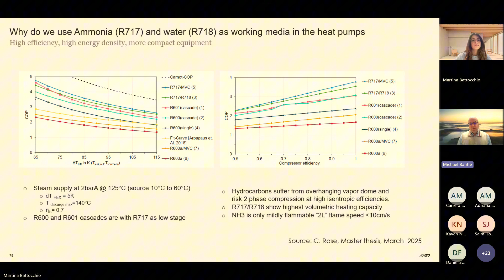why we can operate this heat pump with a really impressive COP of around 3.0, which is what we always say, for a temperature lift of 95 degrees plus minus. This is in a way a good COP. It's a Carnot efficiency of more than 60%, and it is the main reason why we also get quite okay project economics in our economic calculations, together with the operational times.